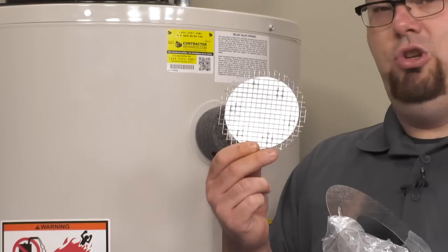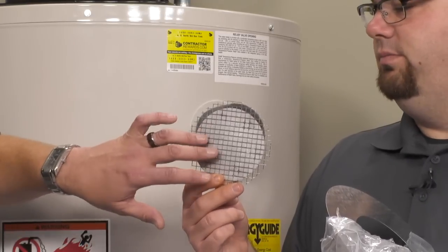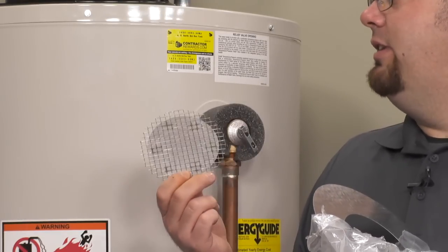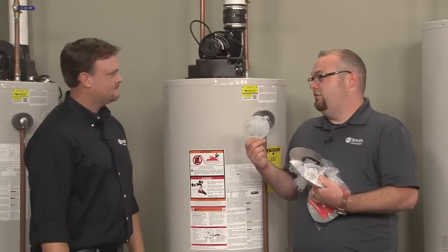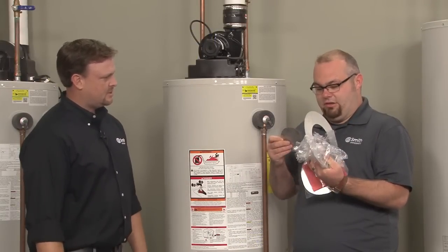For a 4-inch vent, you would use this screen. Yeah, because you've got to build up some more resistance, right? Yeah, you need back pressure. We also need it to meet efficiency for this heater to have a 0.70 energy factor. Keep those flue gases in.